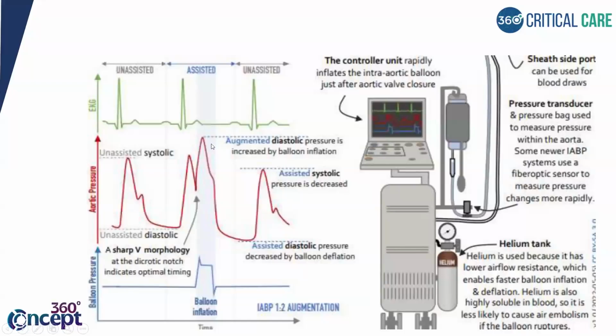So after being assisted by your IABP balloon, you get the next systolic waveform, which is less than the unassisted systolic. So this is your assisted systolic pressure, which is less than the unassisted systolic pressure. Okay. So after that, the waveform continues. And before you get this assisted systolic, you get this assisted diastolic pressure, which is less than the unassisted diastolic. So both your assisted systolic and assisted diastolic will be less compared to your unassisted systolic and diastolic. And you get an augmented diastolic pressure. So this is only possible when you do it in a 1:2 augmentation. Okay. So this is how it looks.